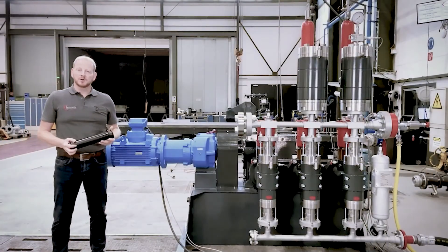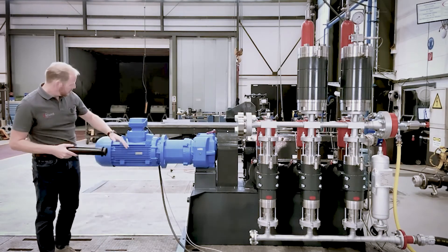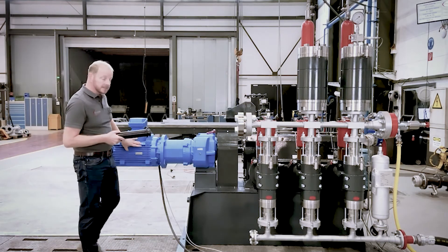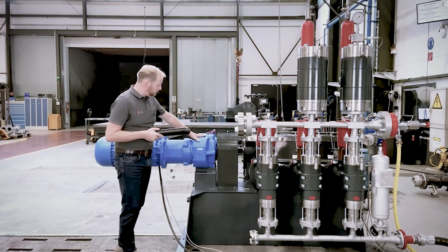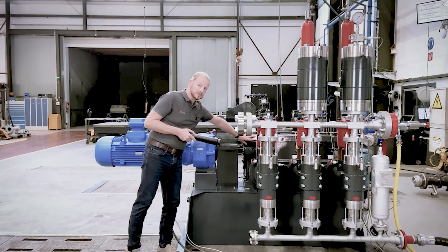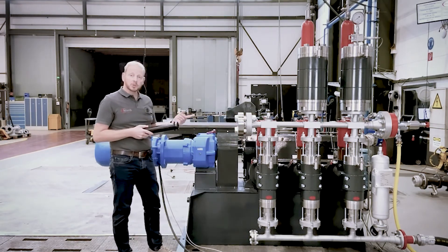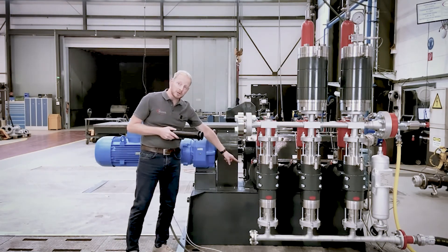Feluwa multi-safe double hose diaphragm piston pump — sounds complicated, but actually the working principle is quite simple. You have your electric motor, whereby its RPM is turned down by an intermediate gear, which is directly coupled to our Feluwa crank gearbox. The crank gear converts the rotary motion of the motor into a linear reciprocating motion of the piston.